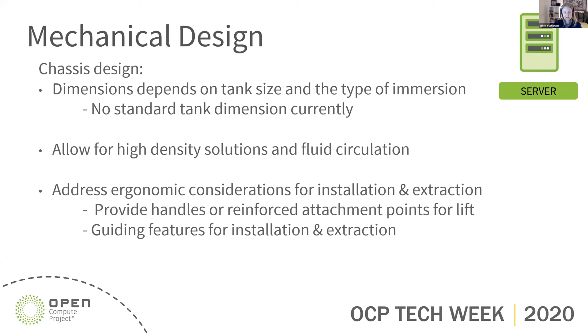The chassis also needs to allow for high density solutions and fluid circulation to make sure that you get that flow of liquid through your IT equipment. You also need to address ergonomic considerations for installation and extraction, provide handles or reinforcement attachment points to be able to lift it out of the tank. Having guiding features for installation and extraction is preferred to make sure that you're not banging the IT equipment into something, another IT equipment box, as you're extracting or installing.